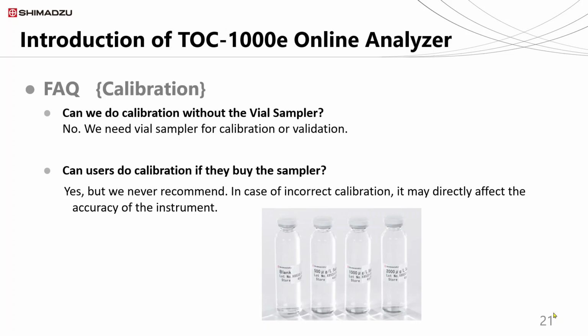Let's talk about some frequently asked questions. Calibration. Can we do calibration without the vial sampler? No, you need the vial sampler for calibration or validation operations. But users don't need to buy the vial sampler optional unit. The Shimadzu local service engineer will bring it to the site when doing installation, calibration, or validation.